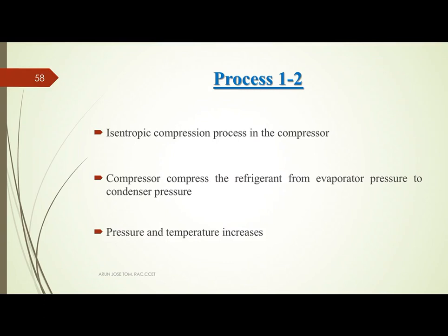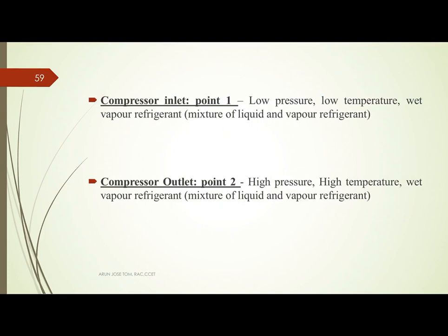The first process is process 1 to 2 — isentropic compression in the compressor. The compressor compresses the refrigerant, which leads to an increase in pressure and temperature, from evaporator pressure to condenser pressure. Point 1 is the inlet condition to the compressor, and point 2 is the exit condition. At point 1, the condition of the refrigerant is low pressure, low temperature wet vapor — a mixture of liquid and vapor.